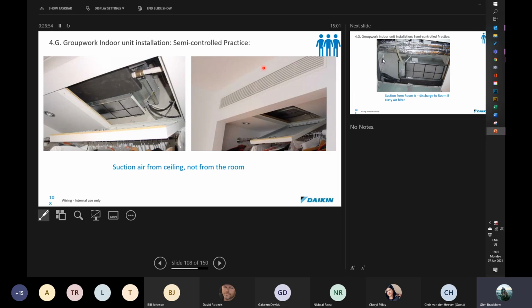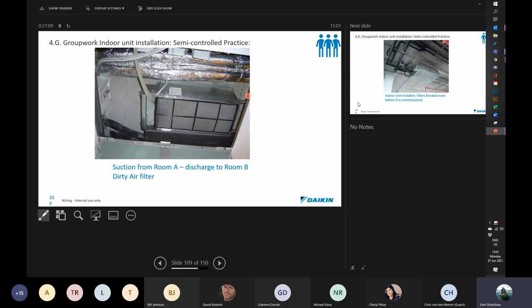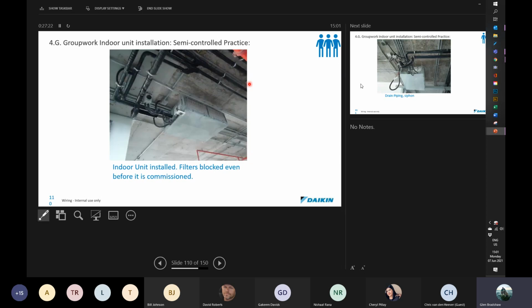Again, also make sure that access to filters is possible. Here we've got an access door, but not much room there as well. And make sure of the different discharge from the rooms. So this is the above one room supplying to another. And over here, if you can see at the back, you can see that these filters are blocked up, and this was even before the unit got to be commissioned.